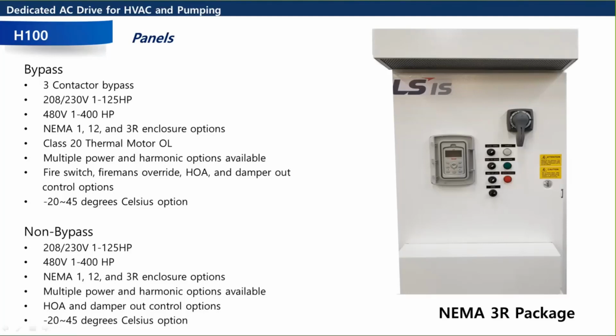So as I mentioned, the H100 goes up to 800 horsepower. So it's approximately a 50% derate. So you can take that 800 horsepower and apply it to a 400 horsepower motor with a single phase in. You're going to have some big breakers and some big input leads, but it's all been UL listed and tested. So yeah, that's a possibility. It's a good question too, because a lot of these pump guys will have a single phase only out in the middle of the field. So that's a good thing to know.